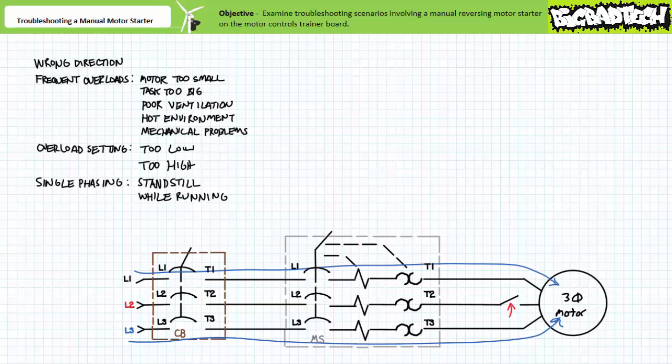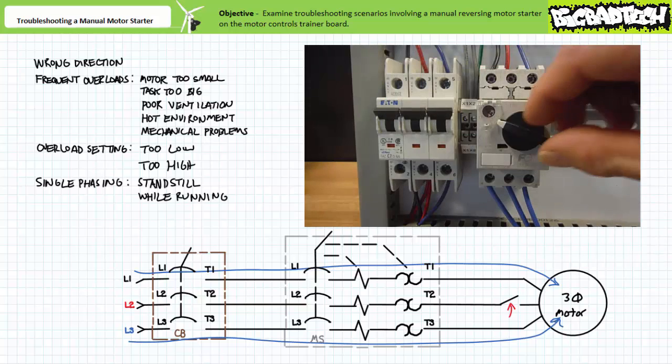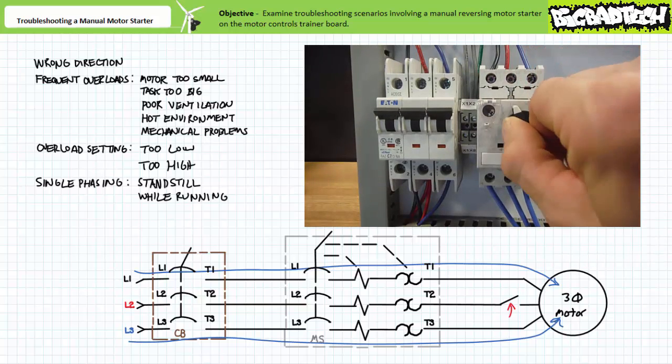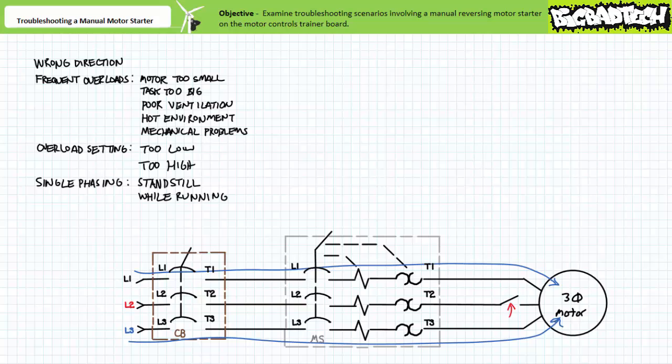Note the manual motor starter is trip free and that it cannot be reset or held in the closed position while the overload elements are still hot. Only when the overload elements have been given a chance to cool will the manual motor starter reset.